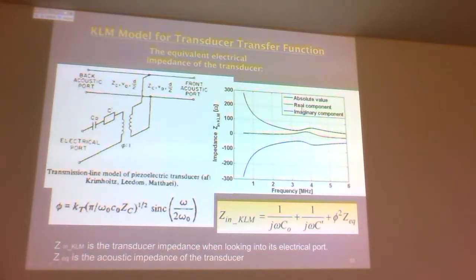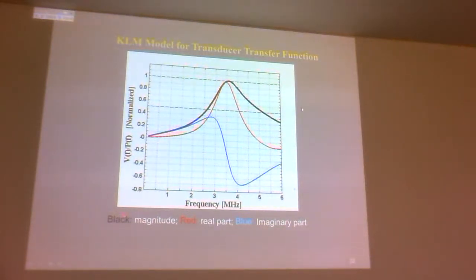We looked at the model of a transfer function, Krimholtz, Leedom, Matthaei. This is an electric model for the transfer function of the transducer that has an amplitude and attenuation, and it gives you the information about the amplitude and the phase of the transducer, or the real and the imaginary component, because this is part of your system. This is what your signal is going to look like. The transducer is going to add to that. And these are some of the responses of these transducers. You can get the magnitude, which is the black, with a peak here at about 3.5 megahertz, the red, which is the real part, and the blue, which is the imaginary part. So you can actually model the transducer that will eventually be taken out of the photoacoustic signal. If you wanted to do true photoacoustic imaging, quantitative imaging, you want to be able to get rid of the transducer contributions. Otherwise, you'll be getting artifacts.